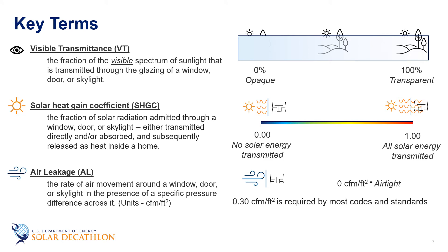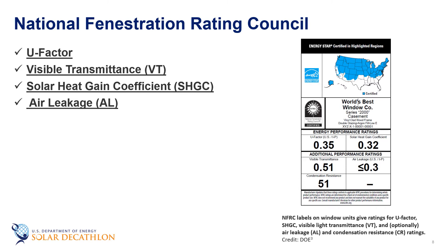Another term you will see often is air leakage, or the rate of air movement through a window, door, or skylight in the presence of a specific pressure difference across it. All of these parameters — the U-factor, the solar heat gain coefficient, the visible transmittance, and the air leakage — are important characteristics of a window that impact its energy performance. They are important enough that the National Fenestration Rating Council developed a standardized label requiring manufacturers to include these numbers on their product.